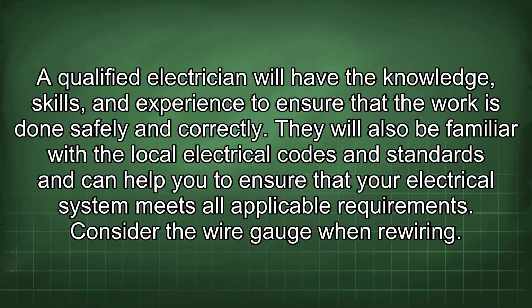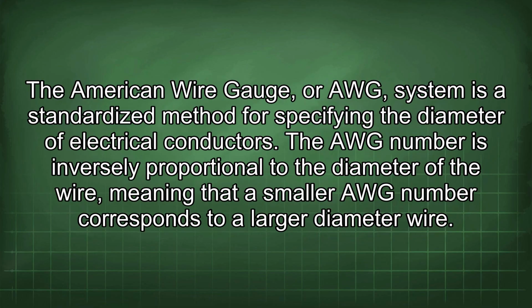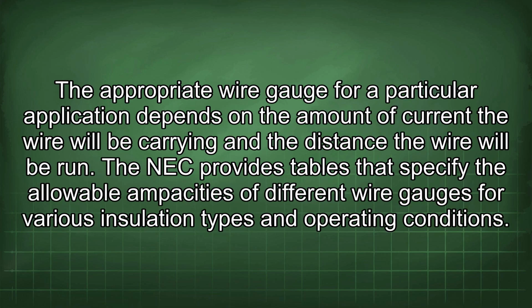Consider the wire gauge when rewiring. The American wire gauge, or AWG, system is a standardized method for specifying the diameter of electrical conductors. The AWG number is inversely proportional to the diameter of the wire, meaning that a smaller AWG number corresponds to a larger diameter wire. The appropriate wire gauge for a particular application depends on the amount of current the wire will be carrying and the distance the wire will be run.